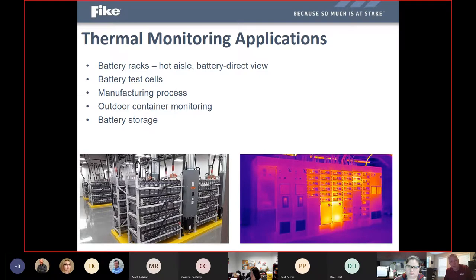Now, thermal monitoring in this regard is not yet recognized in the NFPA codes as an acceptable means of fire detection. So you would still need your traditional smoke or heat detectors in place to actually set off any fire alarms, but this thermal monitoring is more of a prevention or accessory type system, a supplemental system to your fire protection system, because this will give you very early indication of a potential upset condition occurring.